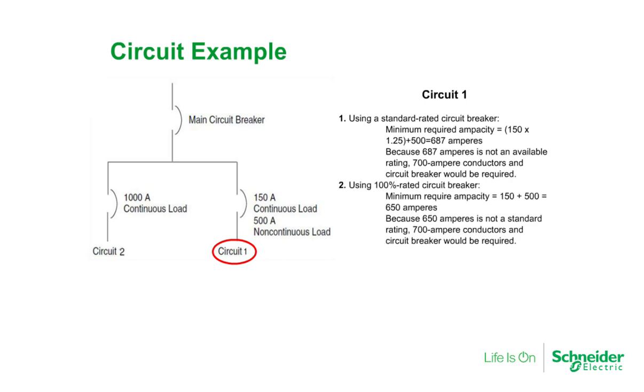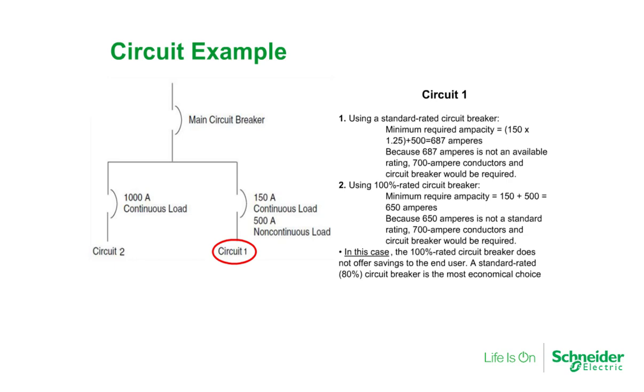When using a 100% rated circuit breaker on circuit number 1, the minimum required ampacity would simply be 150A of continuous load plus 500A of non-continuous load, yielding 650A. Because 650A is not a standard rating either, a 700A conductor and circuit breaker would be required. In this case, the 100% rated circuit breaker does not offer any savings to the end user. A standard rated or 80% rated circuit breaker is the most economical choice.